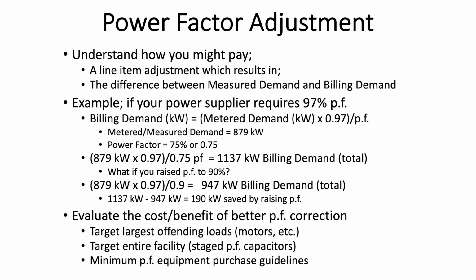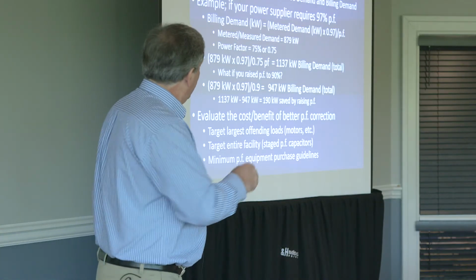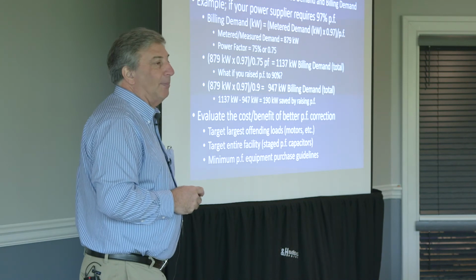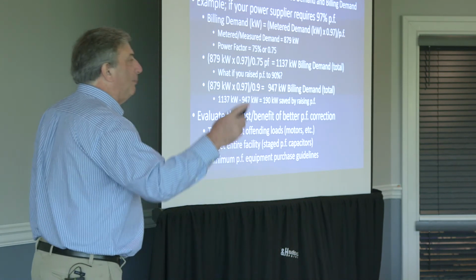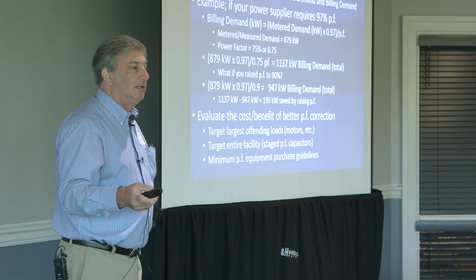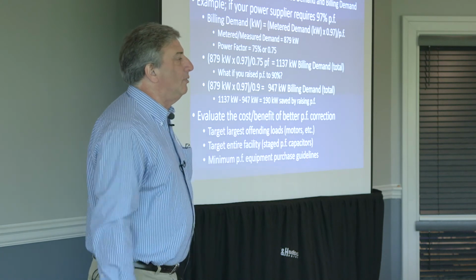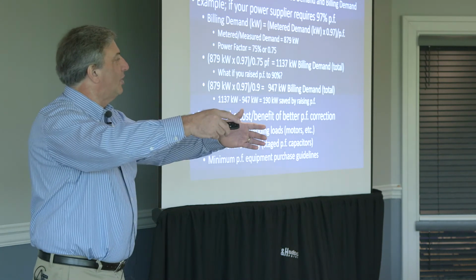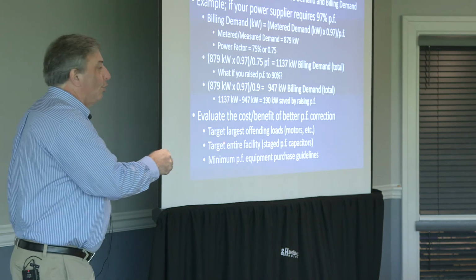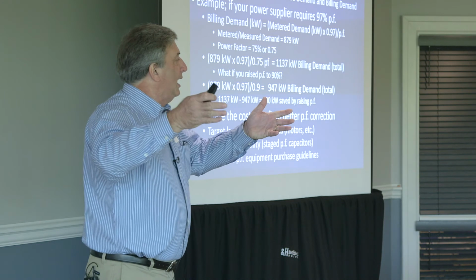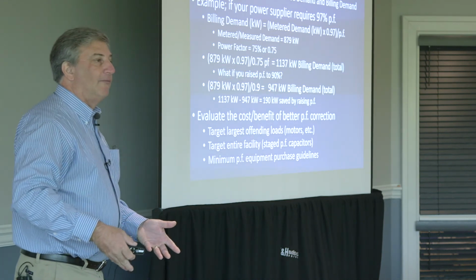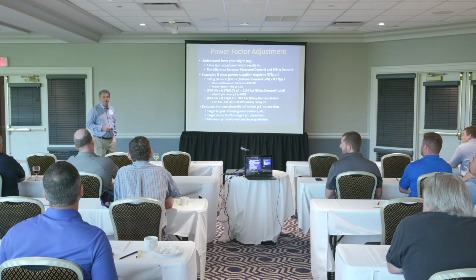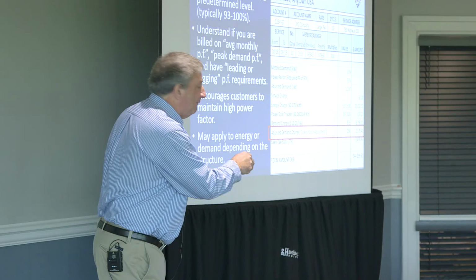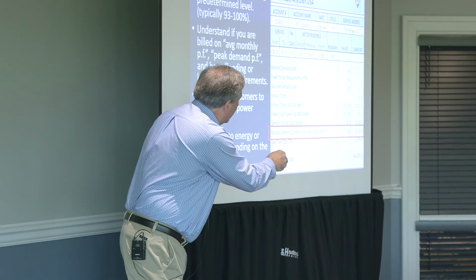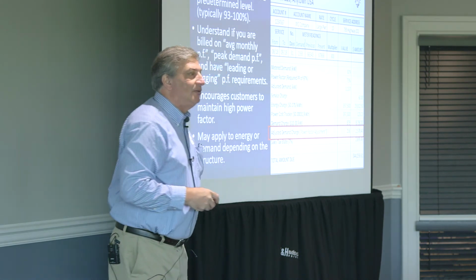Can I target my largest offending motors? Sometimes I've seen plants where it's only 3 or 4 large motors that drag their power factor down. So they can go in and put power factor correction capacitors on that circuit with those 3 or 4 motors, or at the circuit to starter for the 3 or 4 motors. And so as those motors are turned on, the correction is turned on, and when the motors are turned off, the correction is turned off. Does that change the peak demand whenever you do that? Yeah. Now, it may not change, in my example, where I have the peak demand here at 879, no. But now this number goes down by 190 kilowatts.